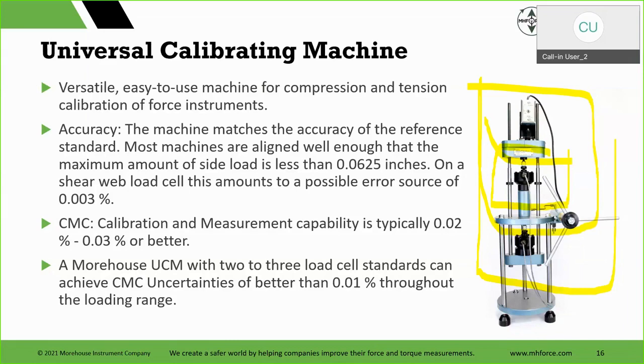same type of calibration on our deadweight machine. We calibrate it with the ball adapter. So you place it in the machine and it's used exactly how it's calibrated. So that is why we say it matches the reference standard. Though there are some additional uncertainties like the side loading and some other things, but really you have a really good reference standard. You're gonna add very little else in this machine.